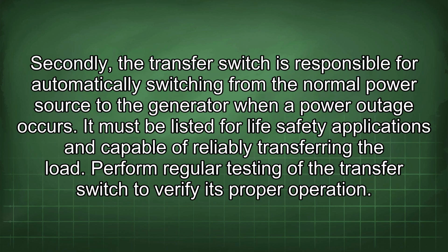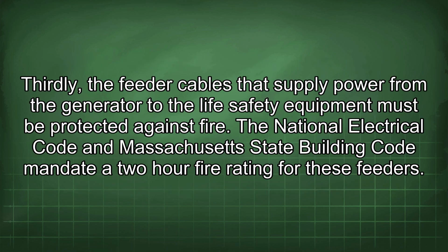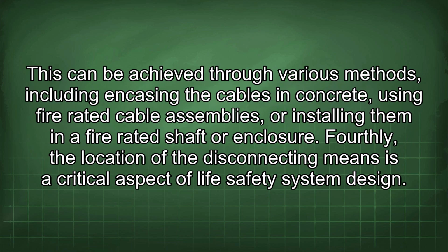Secondly, the transfer switch is responsible for automatically switching from the normal power source to the generator when a power outage occurs. It must be listed for life safety applications and capable of reliably transferring the load. Perform regular testing of the transfer switch to verify its proper operation. Thirdly, the feeder cables that supply power from the generator to the life safety equipment must be protected against fire. The National Electrical Code and Massachusetts State Building Code mandate a 2-hour fire rating for these feeders. This can be achieved through various methods, including encasing the cables in concrete, using fire-rated cable assemblies, or installing them in a fire-rated shaft or enclosure.